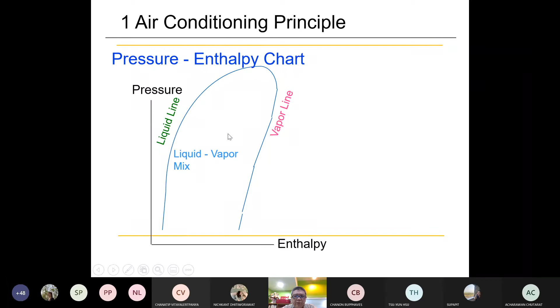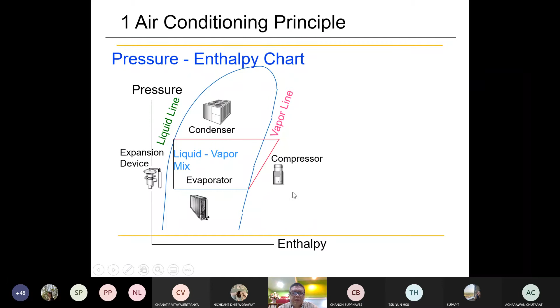So in the evaporator, from the low pressure, this one is the pressure, right? So the low pressure liquid comes to the evaporator and it will fully evaporate. So this one will be low pressure vapor. Then the pressure will be boosted by the compressor. The compressor will increase the pressure. And then it will reject the heat, okay, by using the condenser, from vapor down to the liquid vapor mix and down to the liquid line. After this, it will drop the pressure by using the expansion device. So this is the pH diagram of the simple air conditioning system.